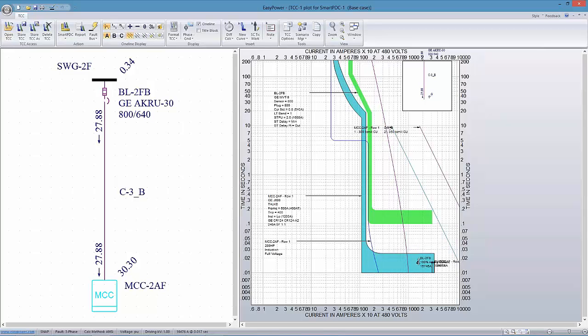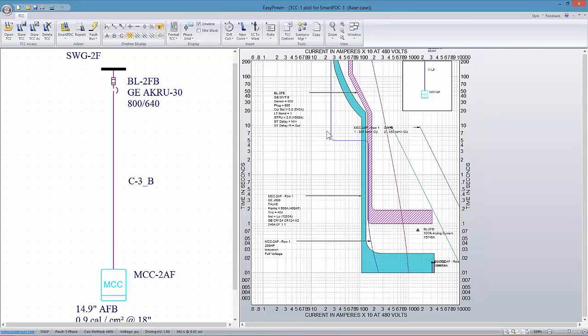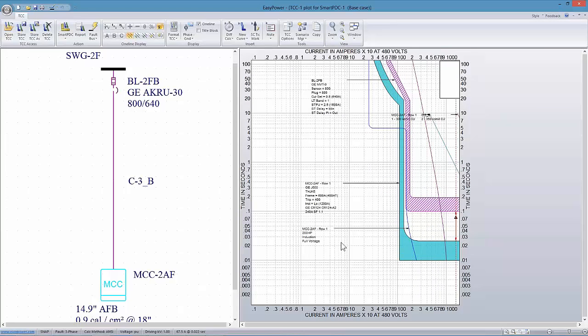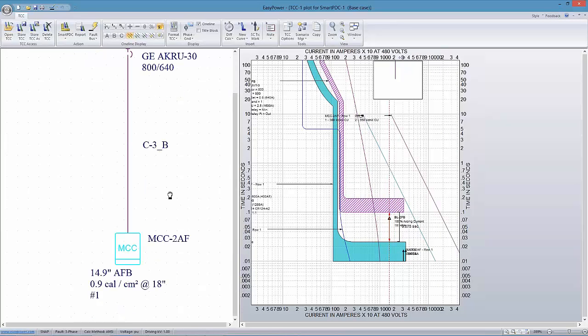So now we're going to look at the arc current that's being used in calculating this energy, and as we look at it, we can see that this energy is being controlled by this particular current and the set points on this upstream breaker. Now, as far as the differences between those two trip points, if this type of fault were to occur downstream, then we could see that at this particular setting, which would be the arcing current that's being used for this calculation, if the fault were a function of the downstream, at any rate, this shows us the ability to see the difference between the two breaker settings, not necessarily applicable to what we're just talking about.